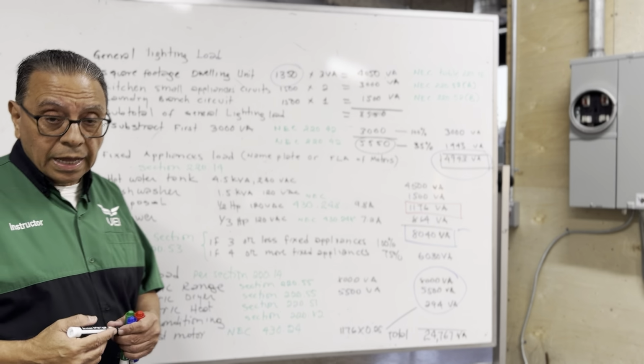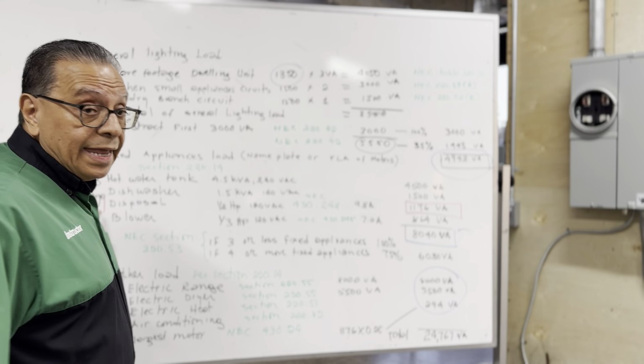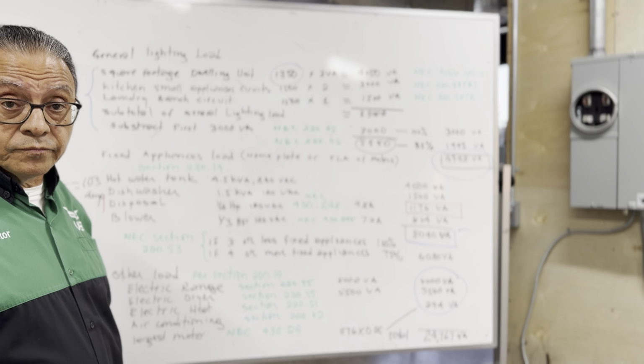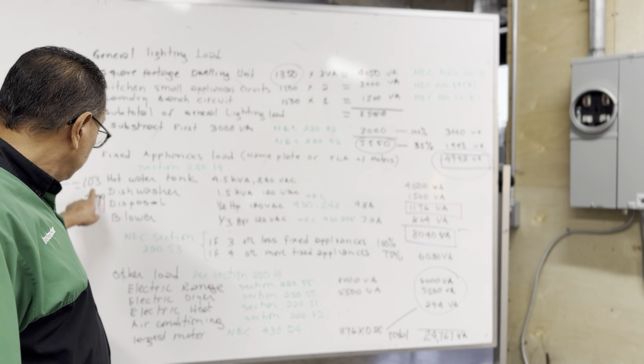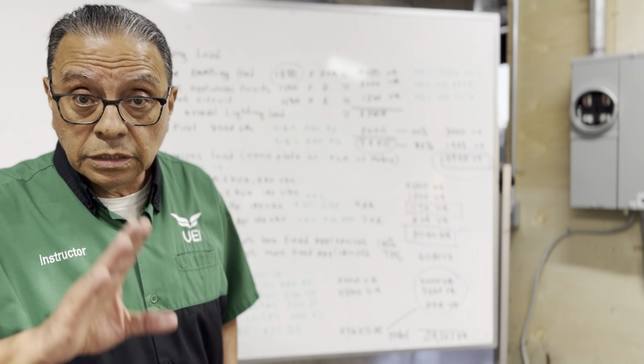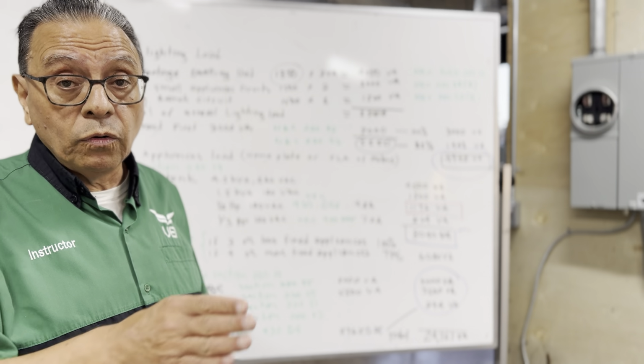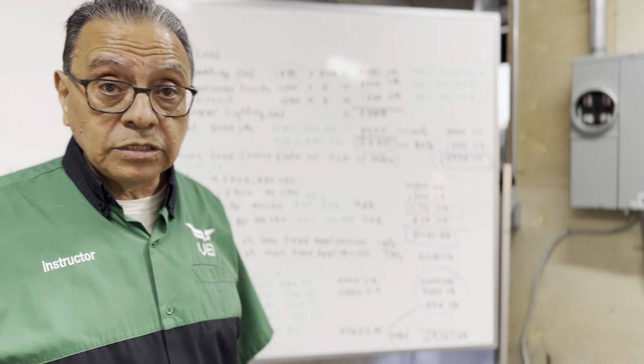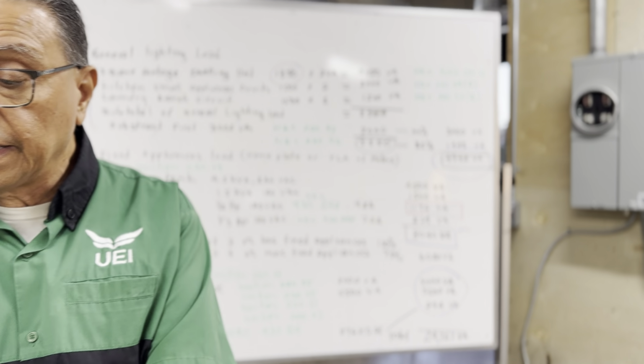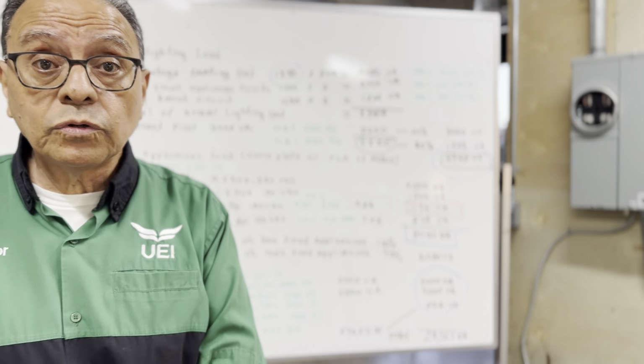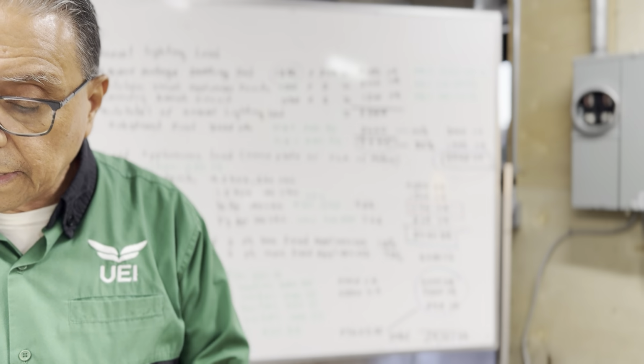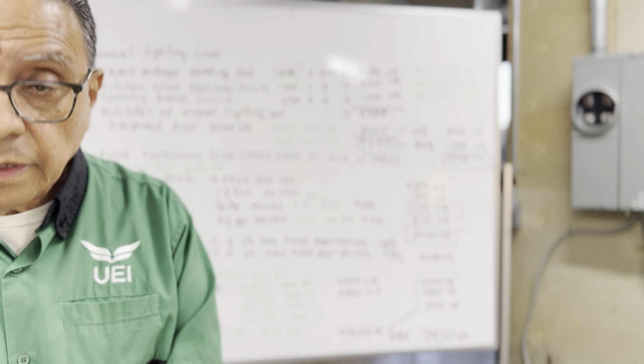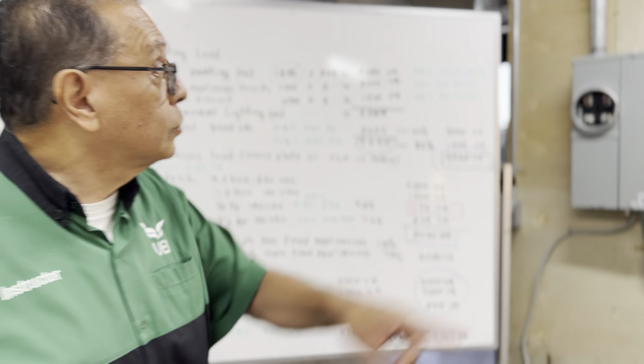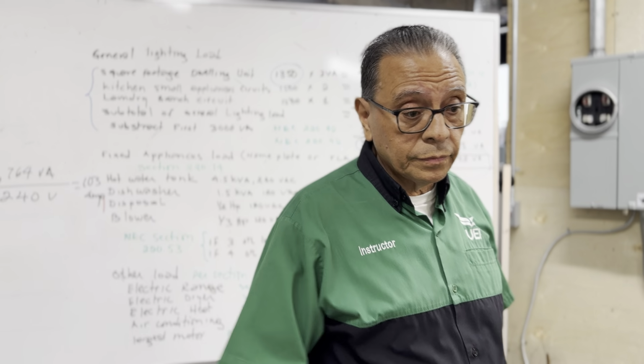So, according to table 310.16, okay, if I use that table, and if nothing is said, I should use the column at 75 degrees Celsius, 167 degrees Fahrenheit, and that table is telling me that the gauge of the electrical conductor providing the power for this service panel should be gauge number 2. Okay, gauge number 2.